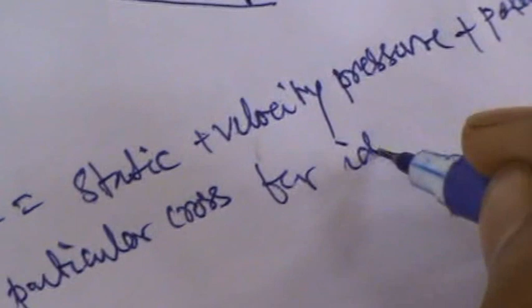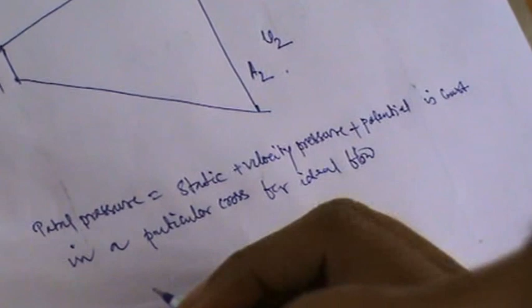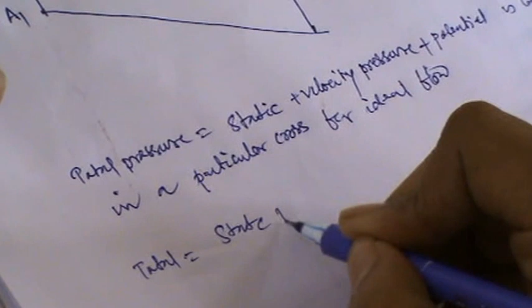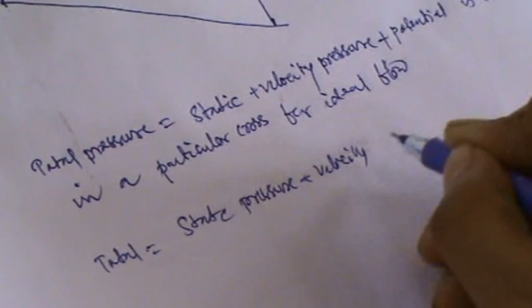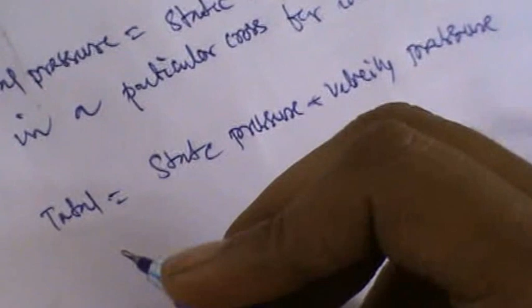As we know, according to Bernoulli's theorem, total pressure equals static pressure plus velocity pressure plus potential pressure, which is constant in a particular cross section for an ideal flow. Therefore, if we ignore the frictional loss or shock loss, and since the potential energy at the inlet and outlet of the evasé does not change, the total pressure, which consists of static pressure plus velocity pressure, remains the same.